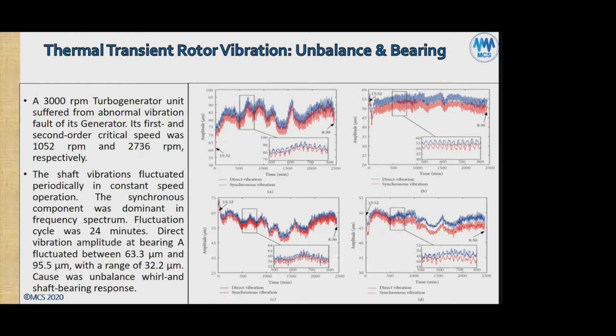So steam exhaust pressure and others. You can add other transient trends that give you more information here. Anyway, what they did when they added the balance weight was they achieved a smooth balance. And so they considered that it was a whirl that introduced this thermal induced vibration at the bearings themselves. This is their interpretation, not mine.